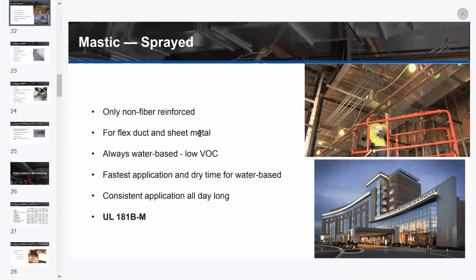There's also sprayable, spray-applied duct sealants, which when you're looking at a sprayed product, of course, it's always going to be non-reinforced. That means there's not going to be any fibers in there to get into your spray pump and cause any clogs. And it's used for flex duct and sheet metal, always water-based, low VOC, and meets the UL 181B-M. And spray-applied is the fastest application and consistent all day long, as you have a pump that's doing the majority of that work for you.